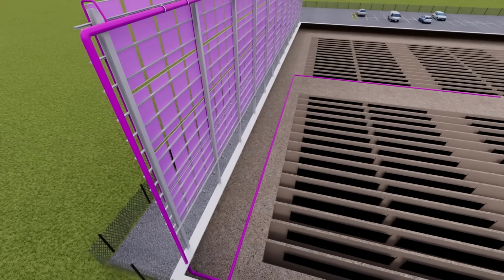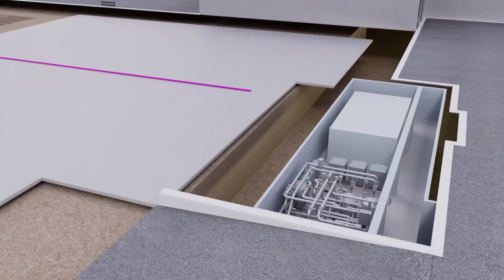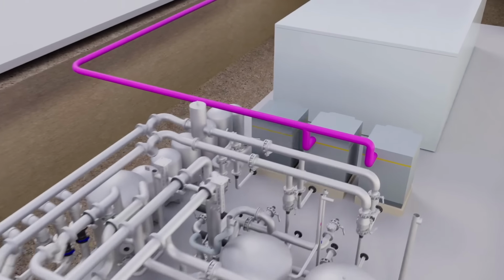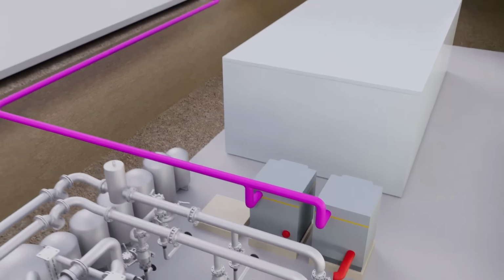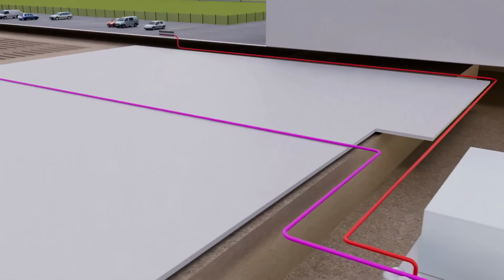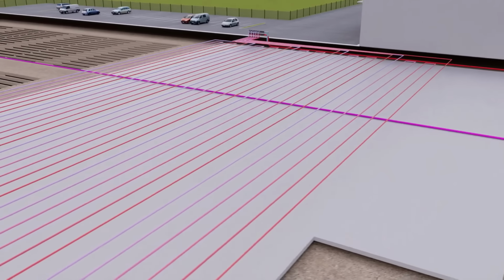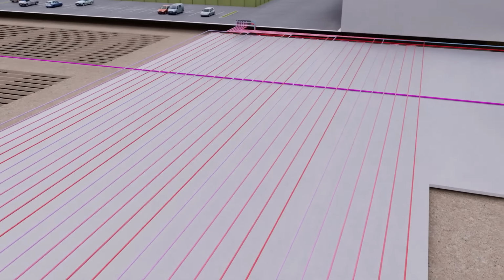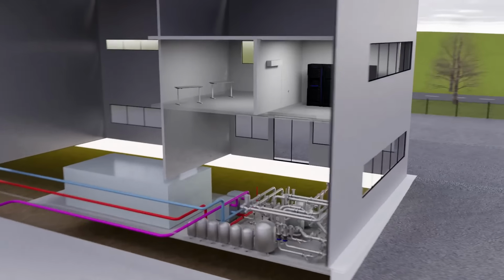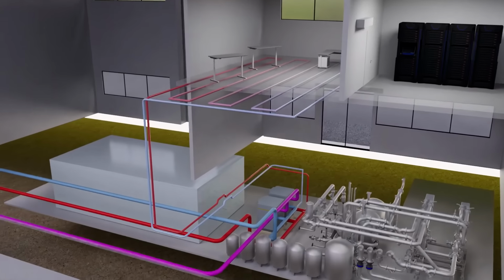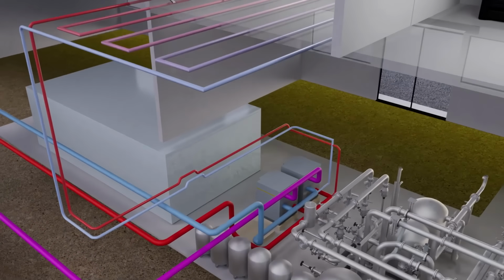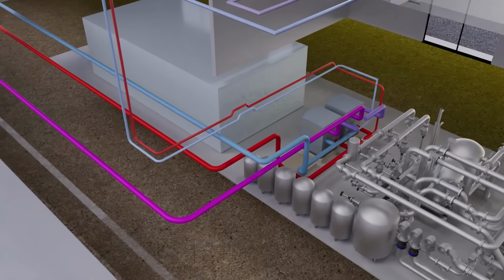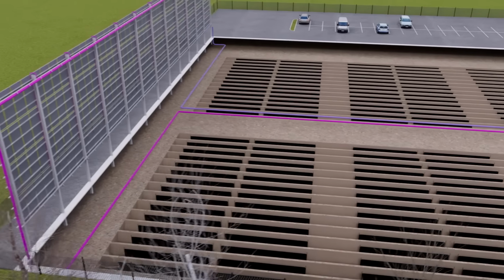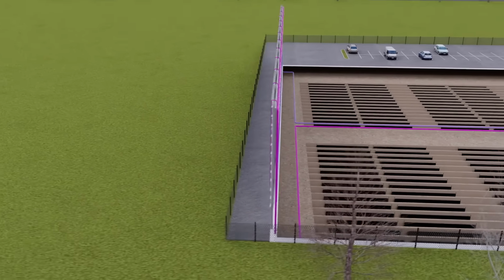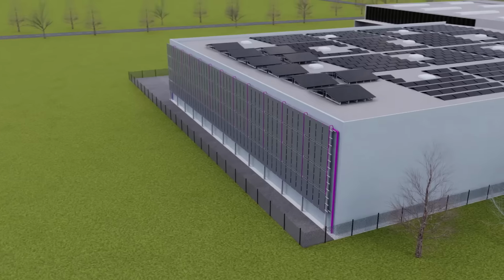The brine, now heated, flows to two of the three heat pumps. These compress the large amount of lower temperature heat to the level required by the concrete core and the underfloor heating in the offices. In the process, the brine cools down again. It then flows back to the absorbers. These ultimately function like the outdoor unit of an air-to-water heat pump. The heat from the ground storage system can be stored for colder days during the winter when there is little to no sun.